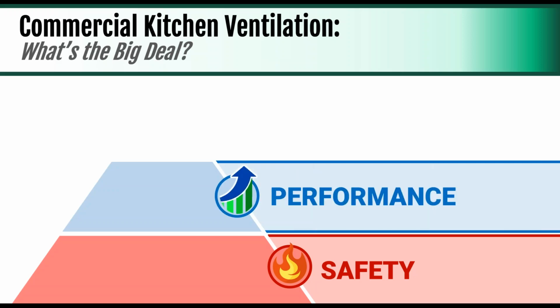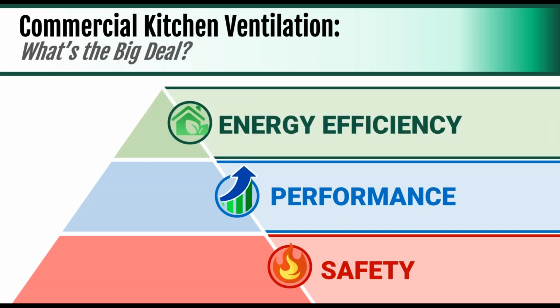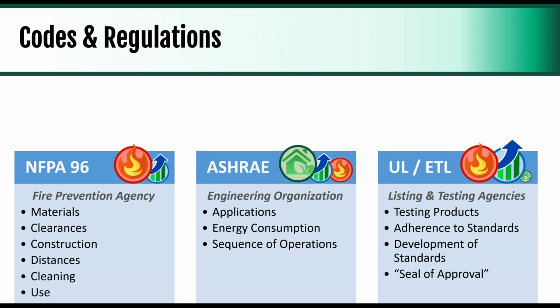Once you've really capitalized on the safety piece, that's when we start talking about performance. By performance, I'm talking about essentially removing all the odors, smoke, and effluent that comes off of cooking and putting it into the atmosphere, which is really the bare minimum hurdle when you're getting into the industry. Where we really focus is what I call the top of the triangle, which is energy efficiency. And so that means being able to do all the performance criteria with the lowest possible amount of energy, and that translates into capital costs sometimes as well.